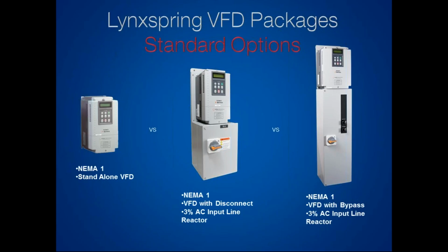And then finally, we've got our VFD with a bypass. A bypass allows you to bypass the drive should you need to. Let's say you're having some sort of issues with your drive, you need to replace it or something's going on. The bypass is an across-the-line starter that's still connected to your motor. So you can still run your motor even if your drive is offline, okay? Having that bypass is basically a backup system. If something fails in the VFD, that bypass will automatically kick over and you won't have any downtime. The bypass will just pick up where the drive left off.